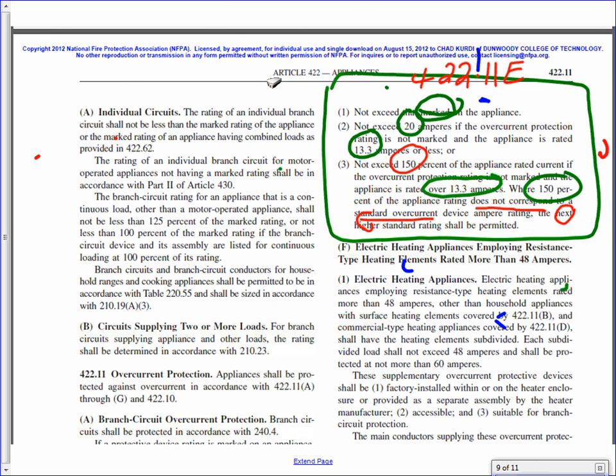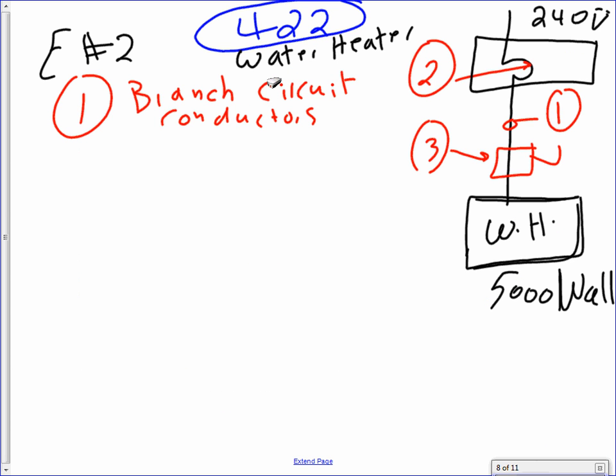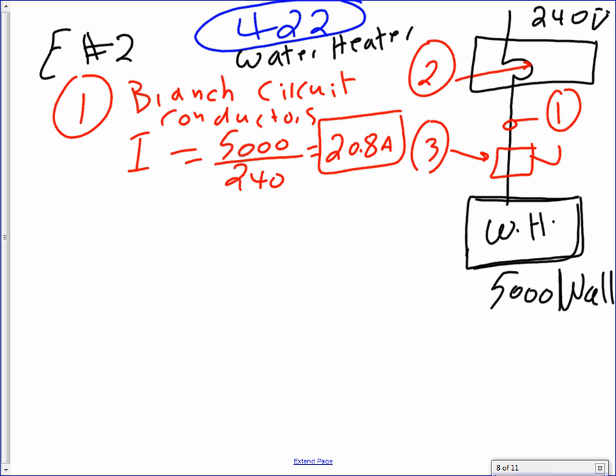Okay. Now let's go apply that one. So that's where the information is coming from. Branch circuits. For my water heater, branch circuits. For my branch circuit, the first thing you need to do is find the I. I equals 5000 divided by 240. Find the full load current because we size things based on current. That'll give me 20.8 amps. The full load current of this water heater is 20.8 amps.